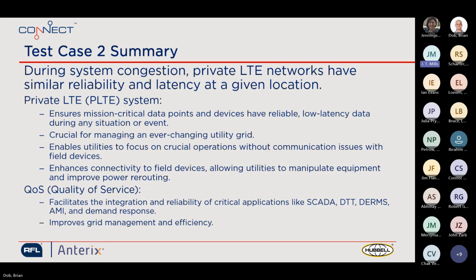So in summary, a PLT allows you to give priority and criticality to your mission critical data points and devices that you prioritize as critically important in the protection field, right? Protection applications are extremely critical to how the utility does fault location, does DER tripping. All those things are very critical, mission critical points. And with PLTE, a private system, you're able to control that and make sure you never lose any reliability or dependability on any of those connection points.